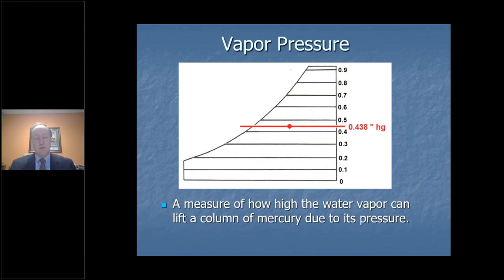Moisture seeks equilibrium. So if you've got an extremely humid day outside and you have done all that you can to dry your building out, and you've run your dehumidification system, your air conditioning system, and you got it nice and comfortable, but you have infiltration from outside. So the moisture that is outside, let's say this is where you are outside, 0.438 inches of mercury, but inside you happen to be somewhere along here, which is going to be a much lower vapor pressure. That weight of moisture will push moisture into your building. So we need to understand that that's the driving factor of pushing moisture from one area to another.